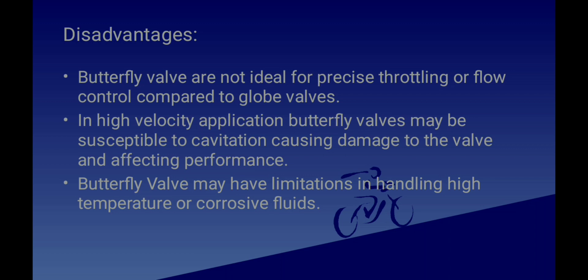Butterfly valves are not ideal for precise throttling or flow control compared to globe valves, and will not give accurate flow control for pipeline systems. In high velocity applications, butterfly valves may be susceptible to cavitation, causing damage to the valve and affecting performance. Additionally, butterfly valves have limitations in handling high temperature or corrosive fluids.